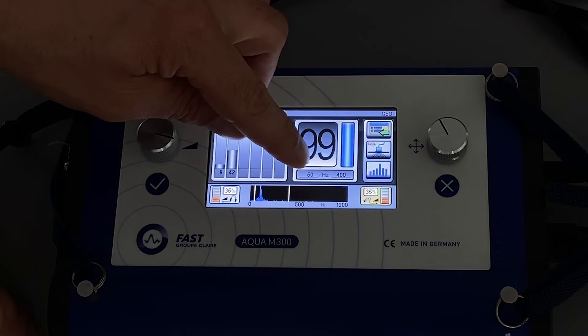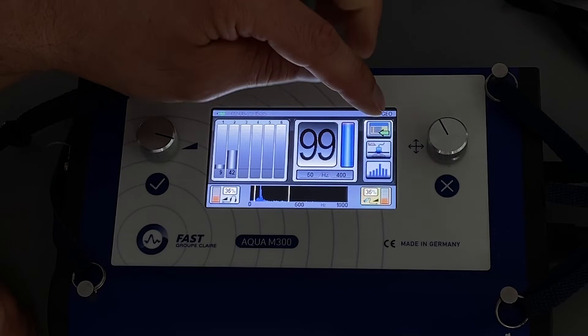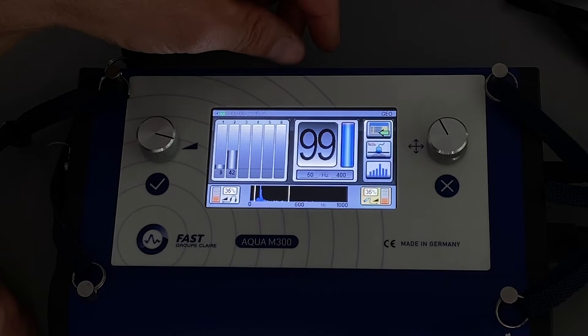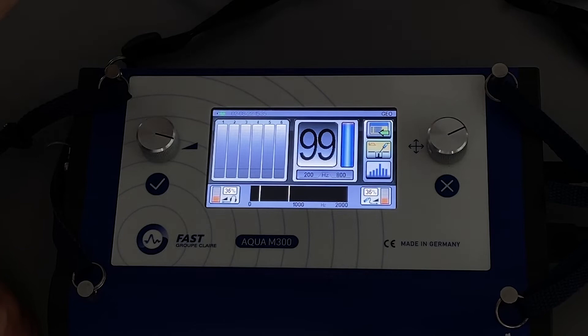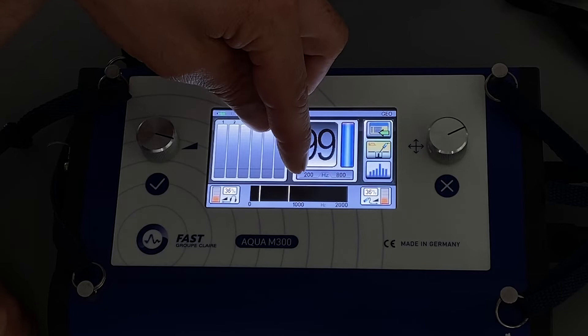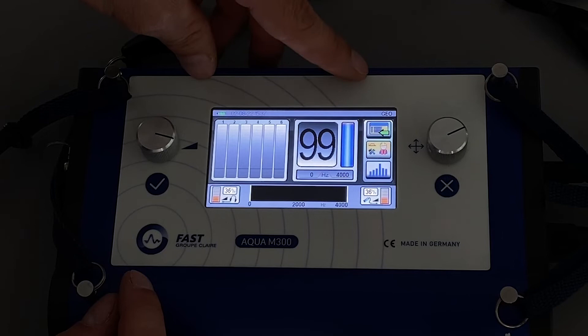Here you switch back to the main menu. Here you have the preset filter settings. In the test rod preset filters the filter range changes — now between 200 and 800 Hz, with a maximum of 2000 Hz available. In the manual filter settings selected earlier in the settings menu, I have completely open filters between 0 and 4000 Hz, which is the full bandwidth shown in the small frequency picture below.